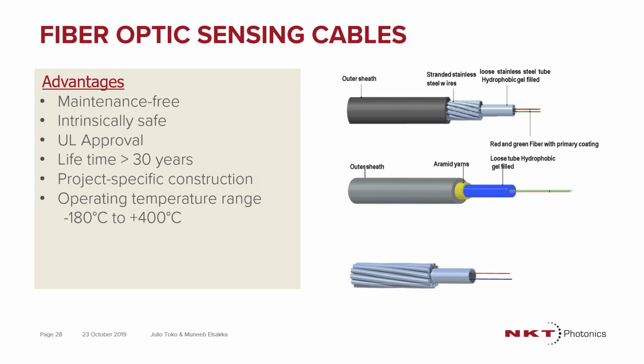The second one, in the middle, is what we call the metal-free cable. This is the type of cable we use in most applications, especially tunnels, such as subway tunnels, where you know you're going to have electrified rails, so you want to avoid using an electric cable. And we have areas, for instance petrochemical plants, where the temperature can be a little lower, or much higher, or cryogenic applications like LNG plants, where you want to do fire detection as well, and then we can use a plastic-free, metal-only type of system. Most of the cables have a very high lifetime, more than 30 years. So it really depends on the application and project-specific construction, and we can work with the engineers to decide which cable will be used.